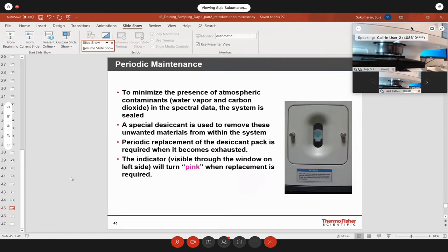Key things is, yesterday one question that was a great question is, what's the regular routine to turn the instrument off and on? I usually leave my instrument on all the time. I would say I basically don't turn it off unless I'm leaving the lab for like 2 weeks or so. The instrument is on all the time.